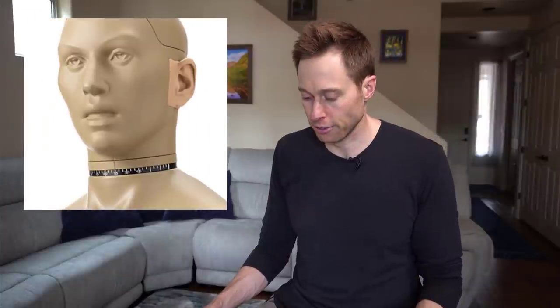The next reason for quality system requirements is a request to broaden the allowance of couplers that can be used for testing devices to include acoustic mannequins like KEMAR. I'll put an image of KEMAR on the screen so you can understand what it is, but typically these diagnostic tests of a hearing aid are done with a 2cc coupler inside a test box. So they just want to expand that and not limit testing to only be done inside a 2cc coupler, which again, I think makes pretty good sense.